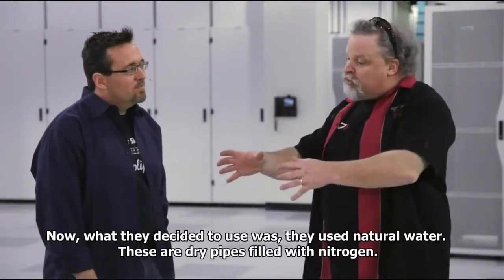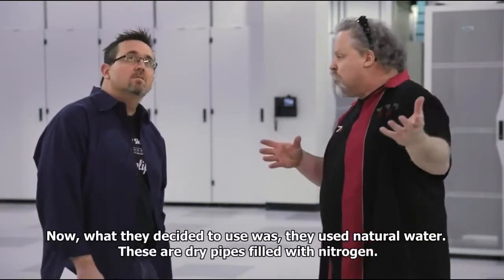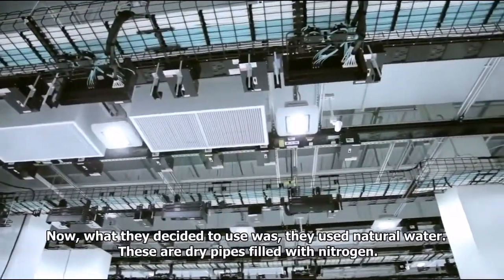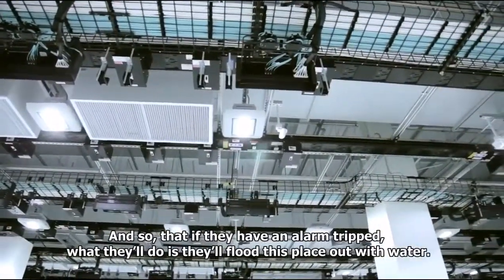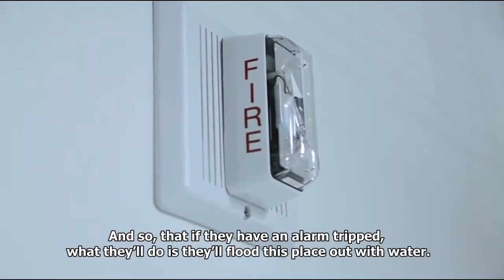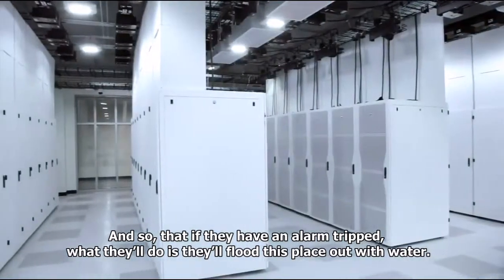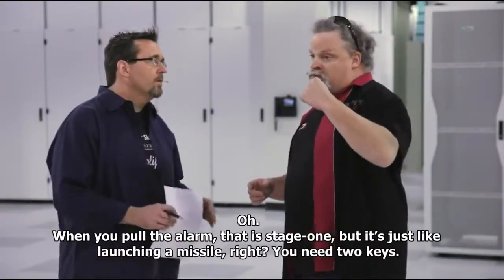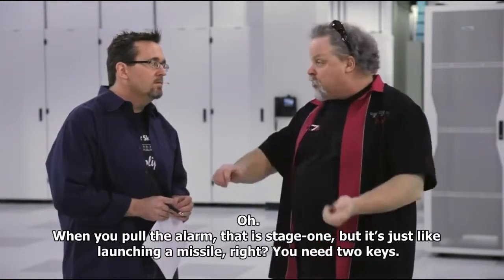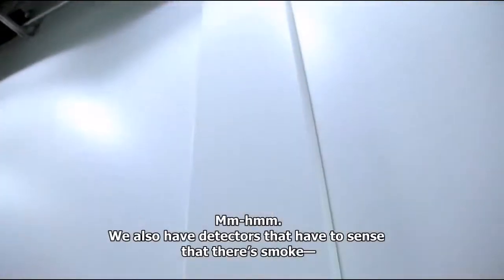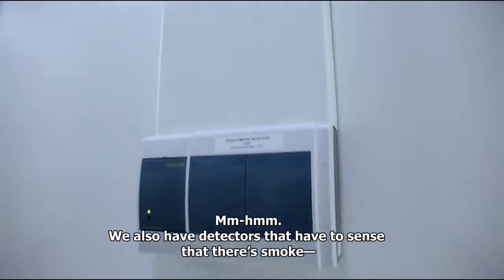What they decided to use here was natural water. These are dry pipes filled with nitrogen, so if an alarm is tripped, they'll flood the place out with water. Now, a couple things here—that sounds pretty scary, but this is a two-way confirmation system. When you pull the alarm, that's stage one, but just like launching a missile, you need two keys. We also have detectors that have to sense that there's smoke.